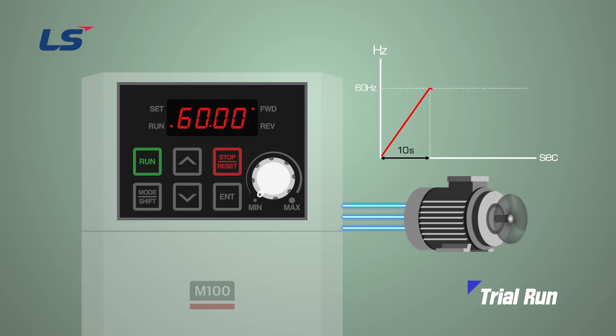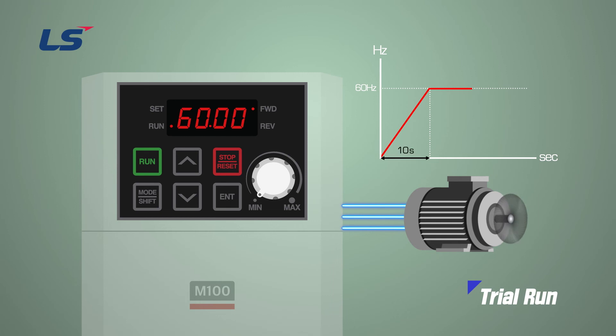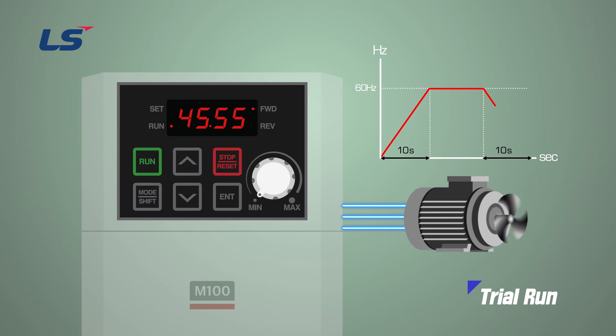So, it will reach the maximum frequency and target frequency of 60 Hz in 10 seconds, which is the previously set acceleration time. If you want to stop, press the Stop/Reset button to decelerate and stop.